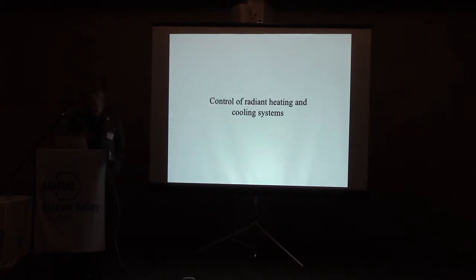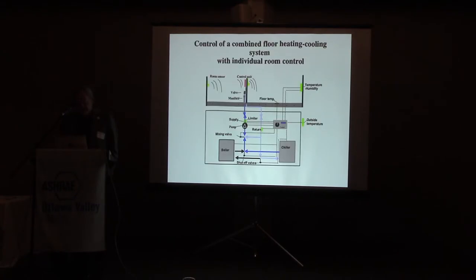Now, how do you control a radiant heating and cooling system? In most cases, this is a little complicated because it's both heating and cooling, but in most cases, when you do the heating part, you have an outside temperature sensor, and you may have a heating curve. Depending on the outside temperature, you find out what the supply water temperature to your house or the zone in the building should be. And that's often how you control it.